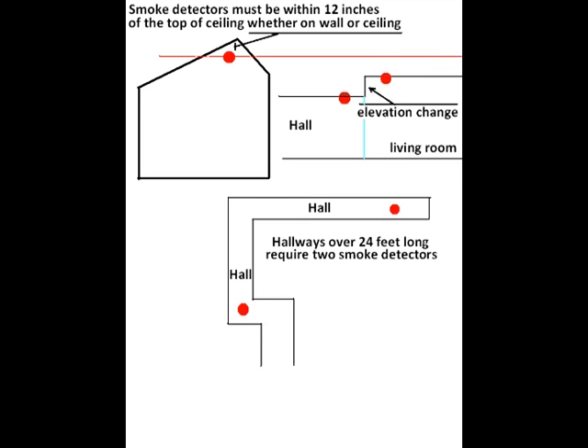Here's some further clarification on smoke detectors. On the top diagram, you see that smoke detector is in a pitched roof or ceiling. That smoke detector has to be within 12 inches of the apex of the ceiling, whether it's on the wall or on the ceiling. It has to be within 12 inches height of the very top of that ceiling.